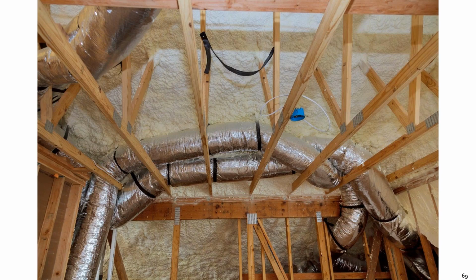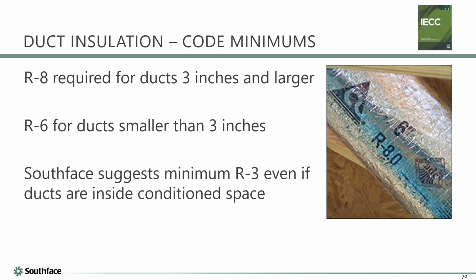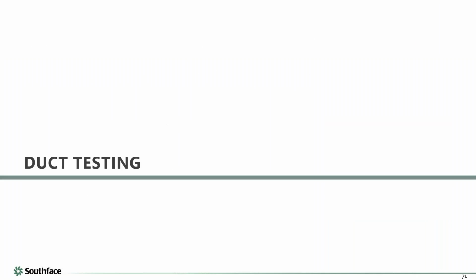And Mike, if you want to tell us why, I think, yeah, it's not going to save any energy, but it is going to not have a cold surface that could sweat. And so the idea that you don't have to insulate a duct if it's inside the envelope, I get it from an energy standpoint, from a heating standpoint, sure, no problem. But from a moisture concern standpoint, I want all my ducts to be insulated. And I believe it's R8 for ducts in an attic too. I think it's R6 for ducts elsewhere. And maybe they changed that for the 18, but I know it's R8 if the ducts are in an attic. So that's easy to look up.